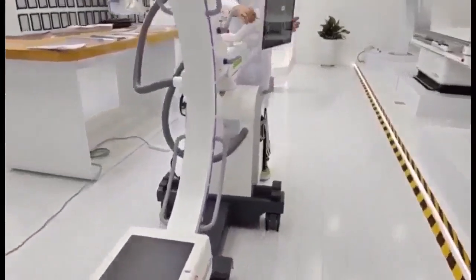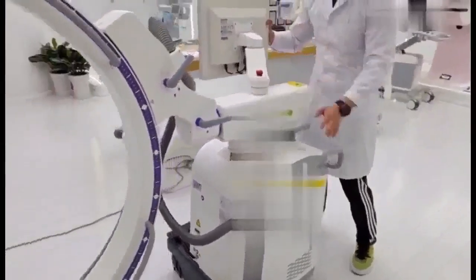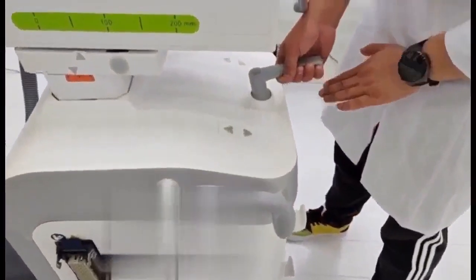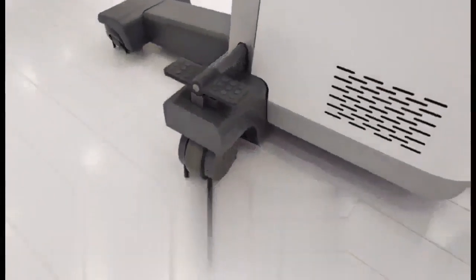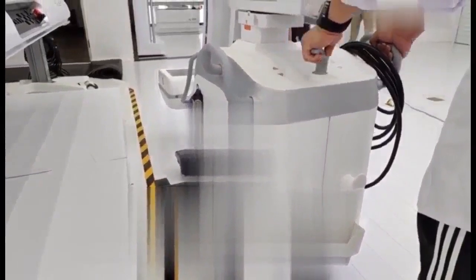To save space when parking the C-arm, most of the time we have to pull away the monitor, and also pull the unit against the wall very near. This is the handle. Lift it up, rotate it left or right for 90 degrees. The wheels will change 90 degrees, then pull it over against the wall. Okay, this is parked. Then use the same handle to let the wheels go back to the normal direction. Okay, this is parked, and lock the main unit. In the same way, we move the mobile console there and park it together with the main unit.